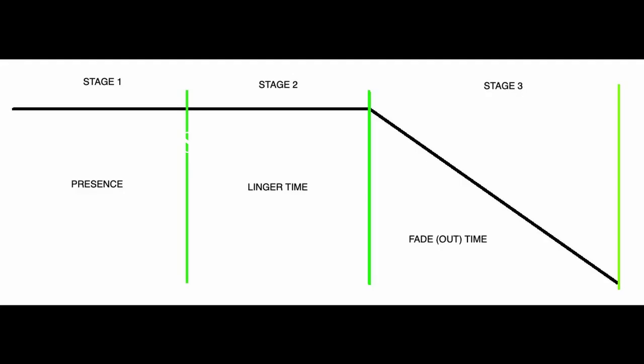What that means is once the sensor has finished detecting presence, the linger time will then start. Once the linger time has ended, the fade time will then start. So there are three stages. The first stage is the time when people walk underneath the sensor and trigger it. The second stage is when the people have walked away and there is no longer any presence, at which time the linger time starts. The third stage is the fade time. Once the linger time has ended, the fade time starts.